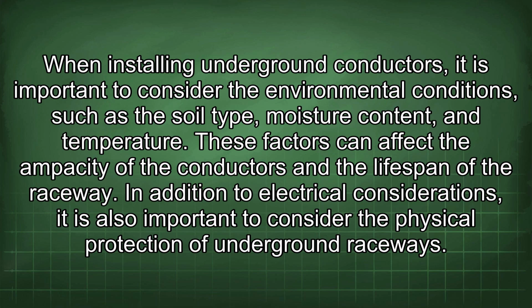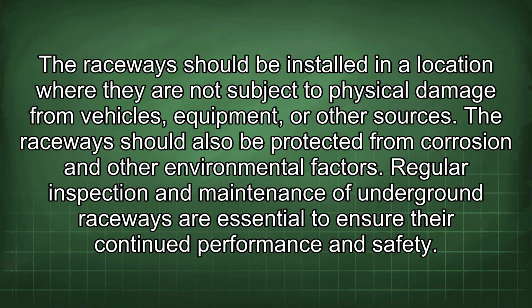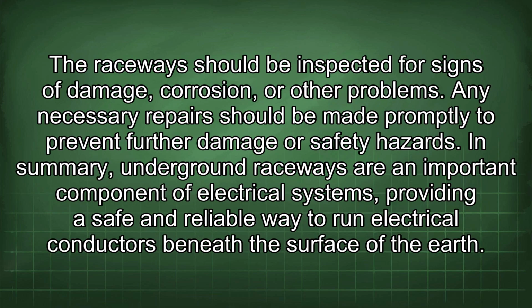In addition to electrical considerations, it is also important to consider the physical protection of underground raceways. The raceways should be installed in a location where they are not subject to physical damage from vehicles, equipment, or other sources. The raceway should also be protected from corrosion and other environmental factors. Regular inspection and maintenance of underground raceways are essential to ensure their continued performance and safety. The raceways should be inspected for signs of damage, corrosion, or other problems. Any necessary repairs should be made promptly to prevent further damage or safety hazards.